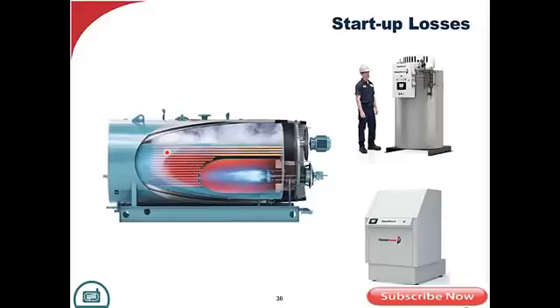But this is really true. These larger mass boilers, once they come up to temperature, they hold that heat. So then once they start getting swings within the load itself, this thing will respond just about as quickly as this one. But it all depends upon that load. Should I go modular, low heating surface, low mass? Should I go larger boiler? Less number, but maybe it's got turn down to match the duplicity that would be required for more modular type units.